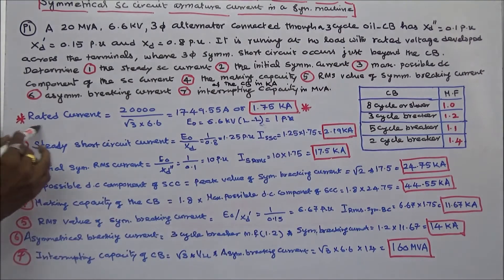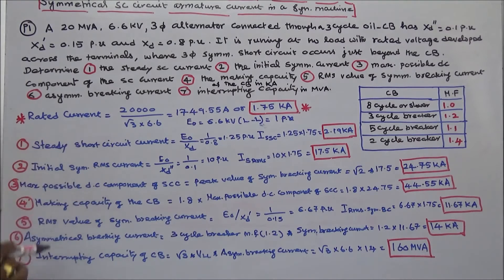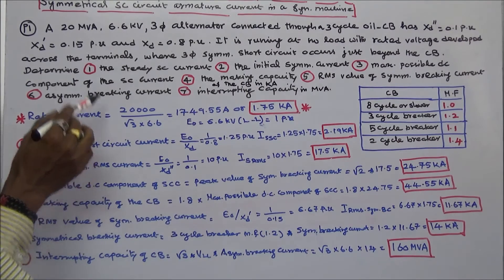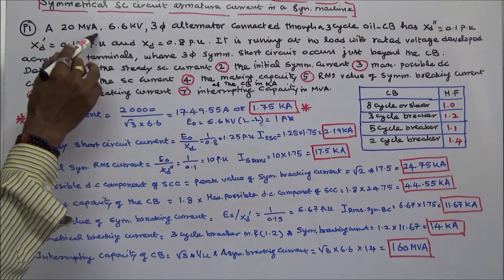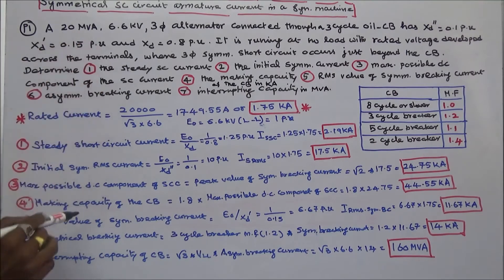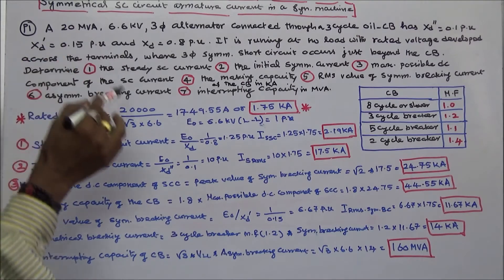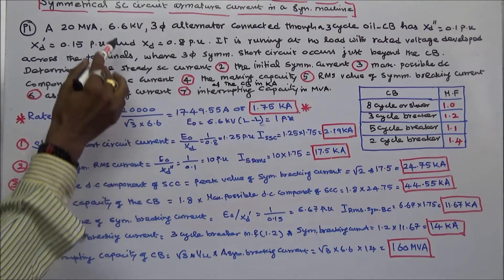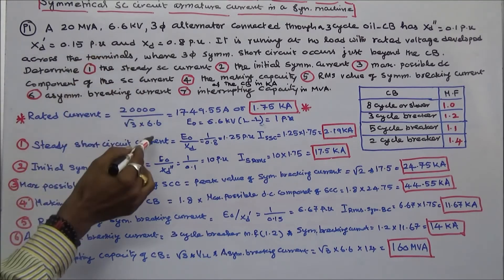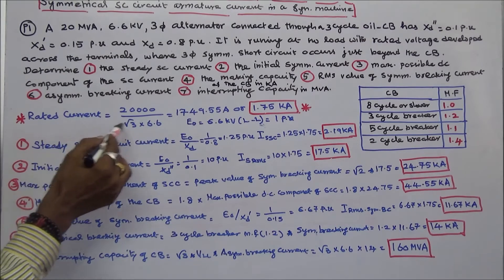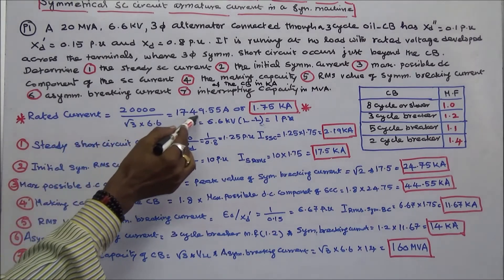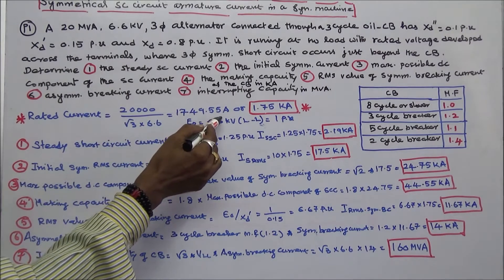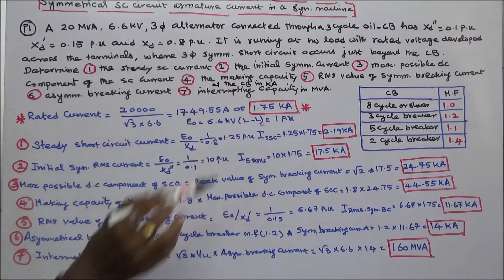First step, we have to calculate the rated current. Rated current is equal to MVA divided by root 3 into 6.6 KV. That is 20,000 KVA divided by root 3 into 6.6, which gives rated current as 1749.5 A, or approximately 1.75 kA.